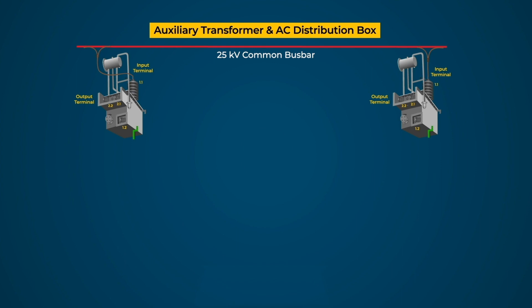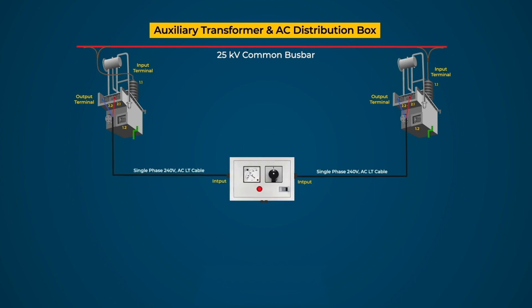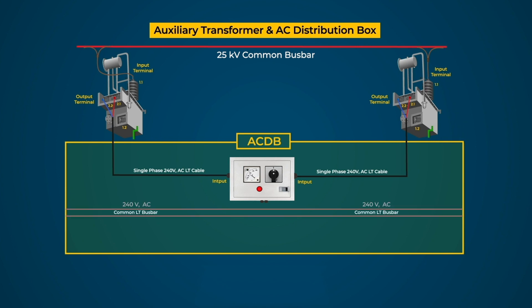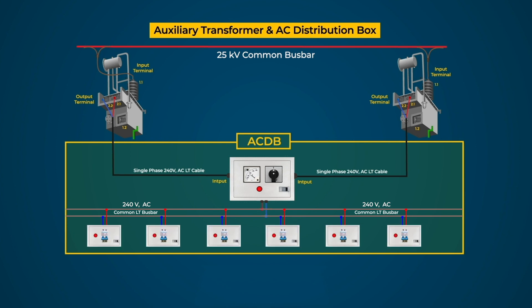The output of Auxiliary Transformers are connected with double-pole switch fuse units of appropriate rating to the ACDB, in such a manner that only one supply is fed to the copper bus bar of the ACDB through a changeover switch. This supply is further extended from the AC bus bar to both the battery chargers.